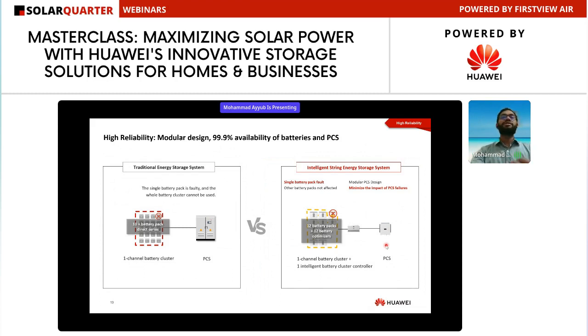The key advantage compared to traditional centralized solutions is that our system is modular. Each component has very low capacity, and we add more capacity by adding more components in series and parallel. On the PCS side, our PCS capacity is 100 kilowatts, which is small, but if the required capacity is 500 or 600, we connect more PCS units in parallel to achieve it. In traditional systems, the PCS capacity is 1 or 2 megawatts, very large.